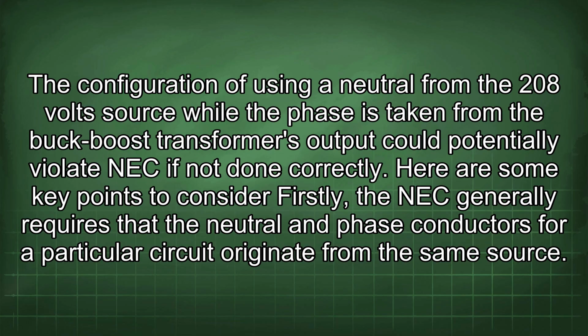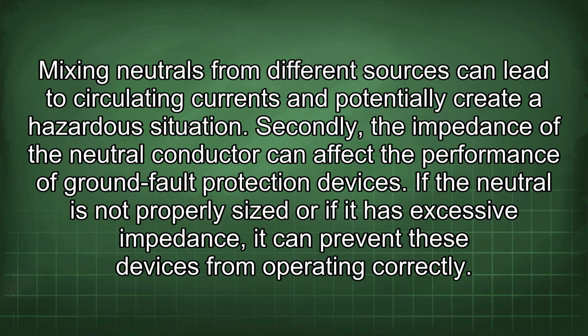The configuration of using a neutral from the 208 volt source while the phase is taken from the buck-boost transformer's output could potentially violate the NEC if not done correctly. Here are some key points to consider. Firstly, the NEC generally requires that the neutral and phase conductors for a particular circuit originate from the same source. Mixing neutrals from different sources can lead to circulating currents and potentially create a hazardous situation.